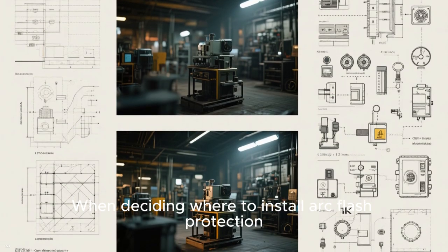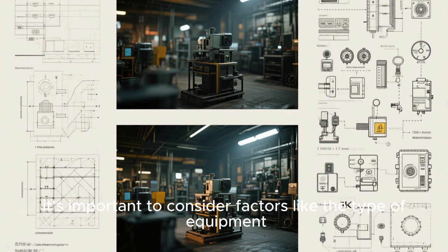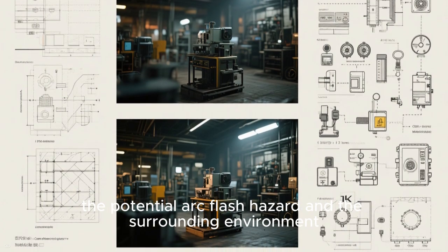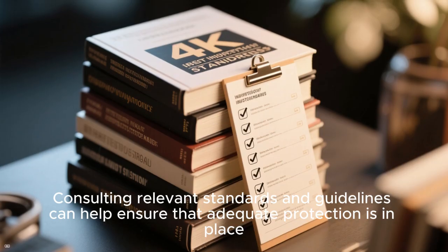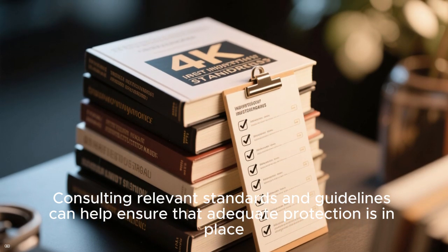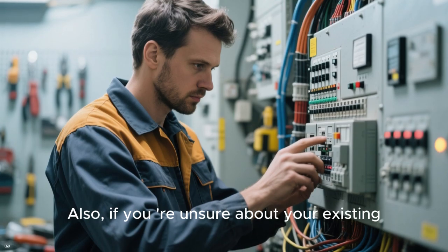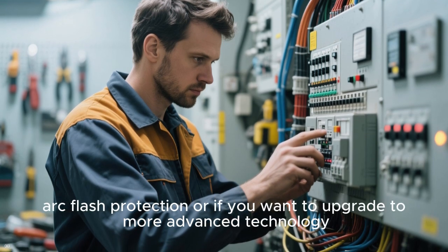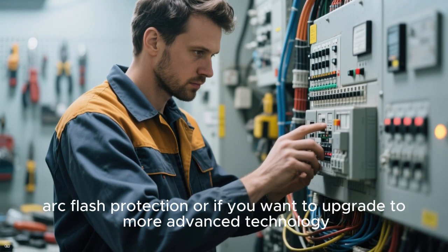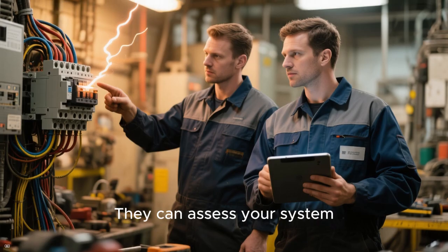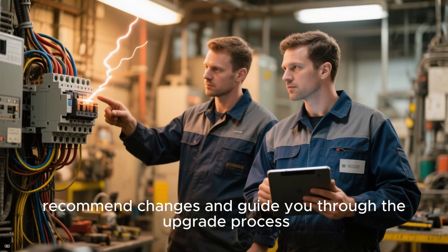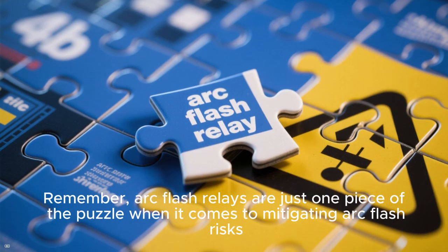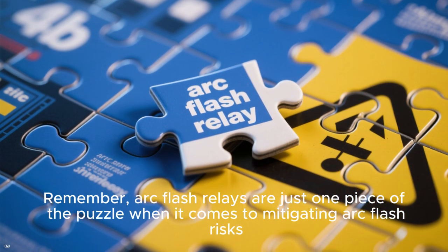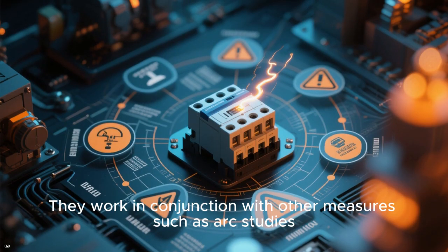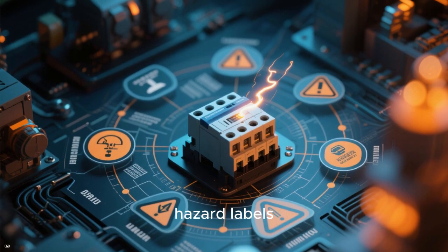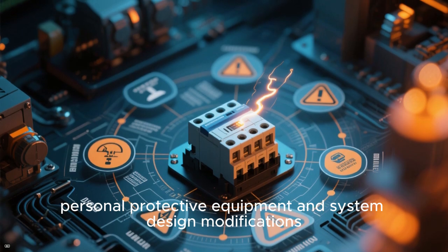When deciding where to install arc flash protection, it's important to consider factors like the type of equipment, the potential arc flash hazard, and the surrounding environment. Consulting relevant standards and guidelines can help ensure that adequate protection is in place. Also, if you're unsure about your existing arc flash protection, or if you want to upgrade to more advanced technology, reach out to a qualified electrical professional. They can assess your system, recommend changes, and guide you through the upgrade process. Remember, arc flash relays are just one piece of the puzzle. When it comes to mitigating arc flash risks, they work in conjunction with other measures such as arc studies, hazard labels, personal protective equipment, and system design modifications.